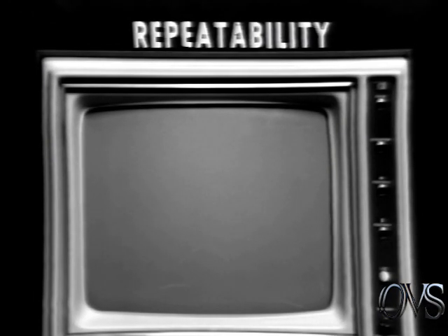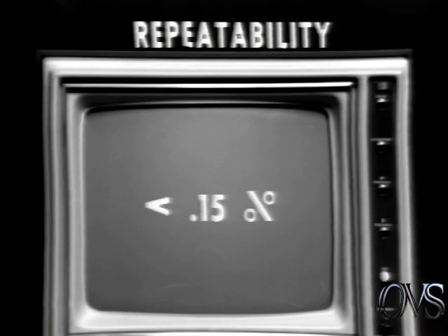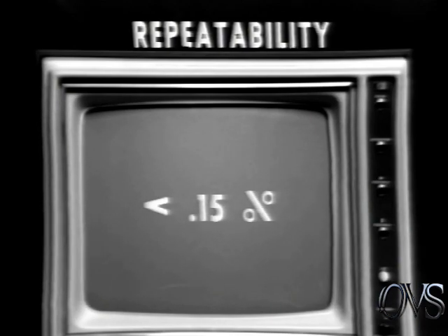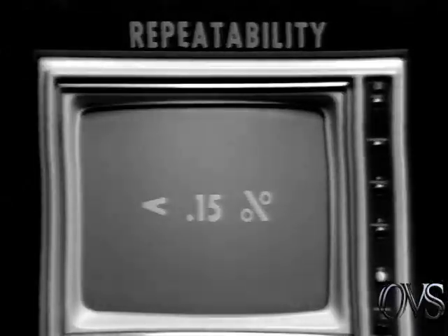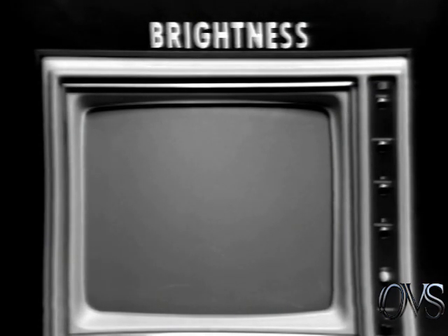Repeatability. When the deflection inputs are repeatedly returned to any arbitrary voltage levels from any on-screen position, the beam will always return to the same point on screen, within 0.15% of full screen deflection. Finally, brightness. This specification is difficult to measure since most users don't have the necessary equipment. However, a simple diagram of the test setup looks like this.